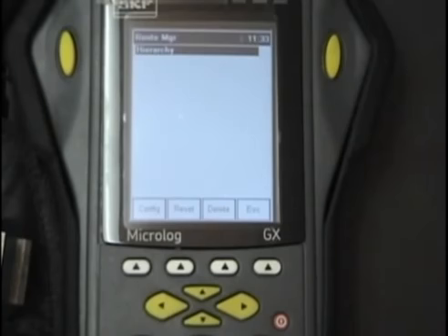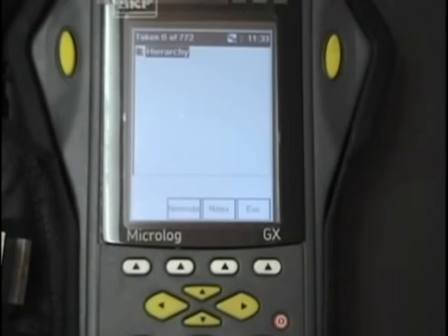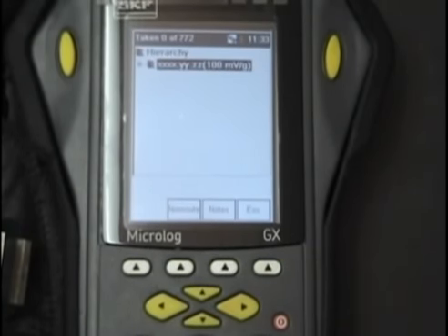Hierarchy will appear and be highlighted. Press the right arrow key. Press the right arrow key again, and you'll see a serial number and sensitivity that should be identical to what is on our transducer. If it is not the same, return the unit, get another one, and use it on the test. If it is the same, go ahead and use this one.